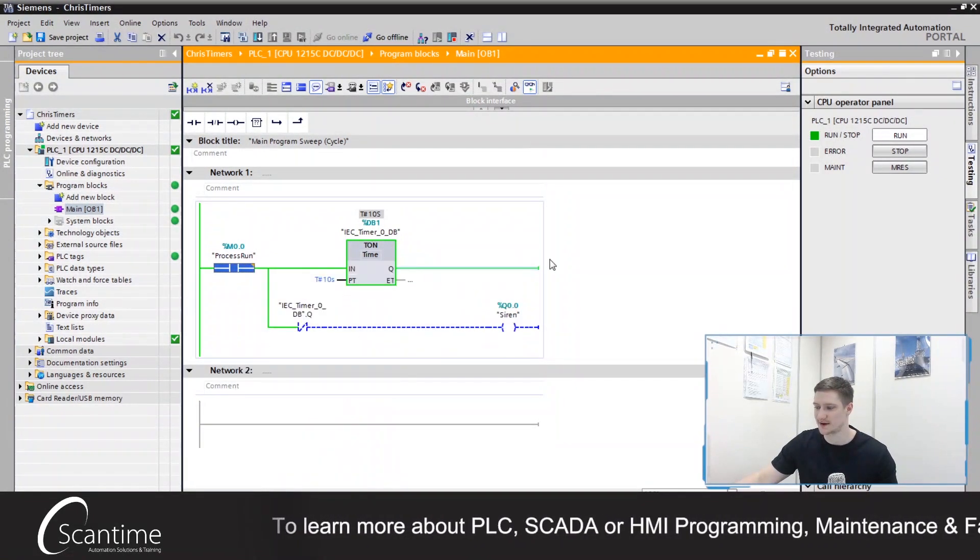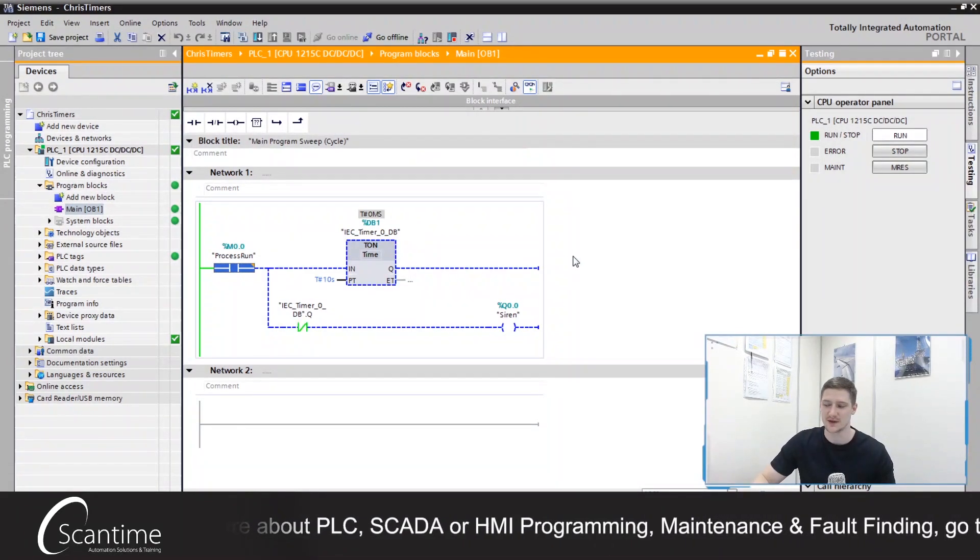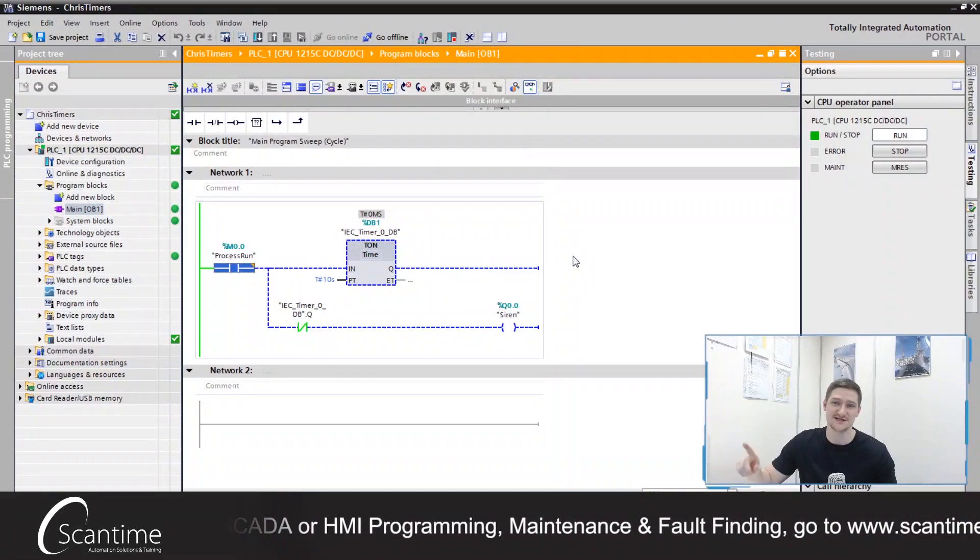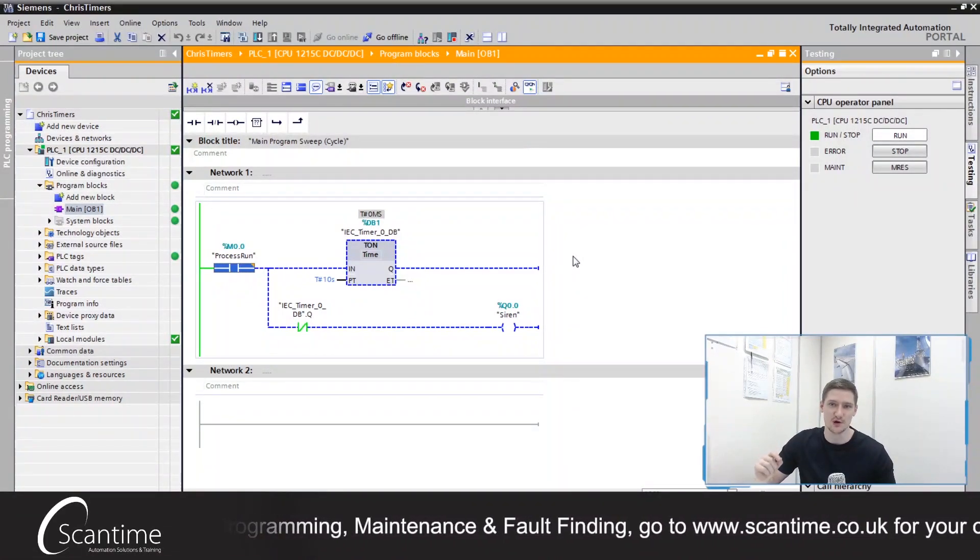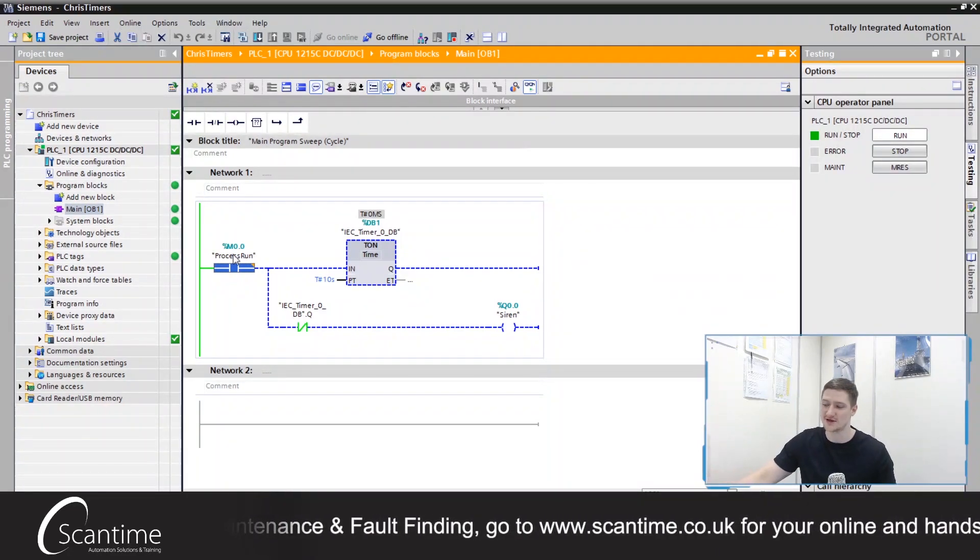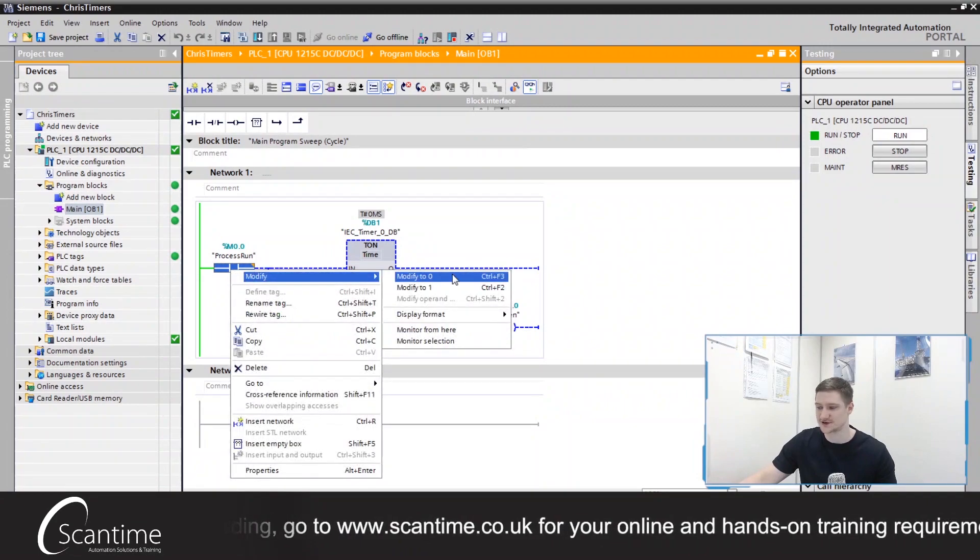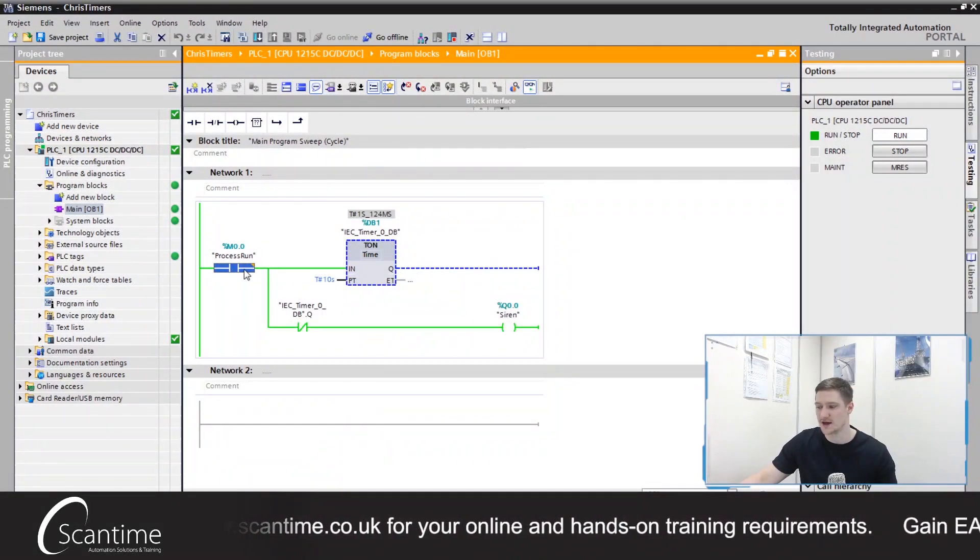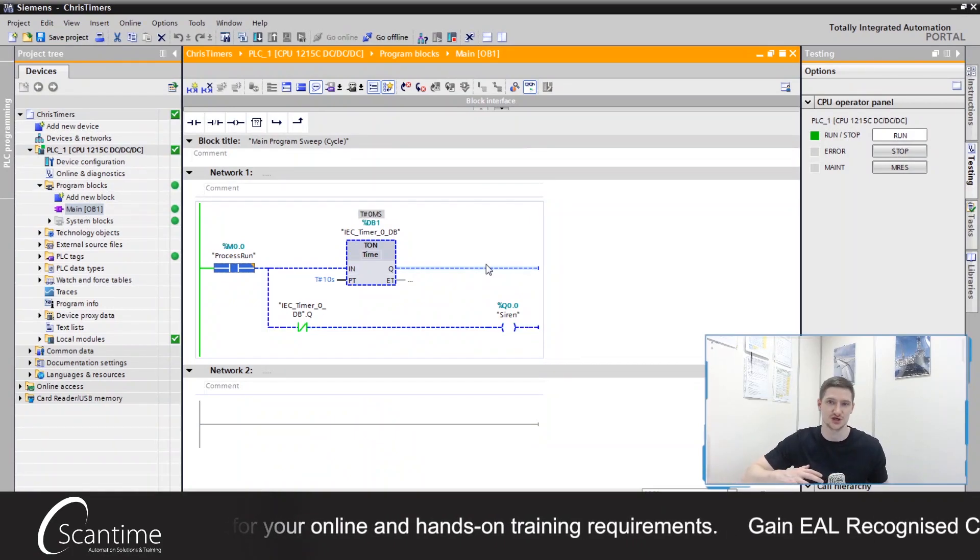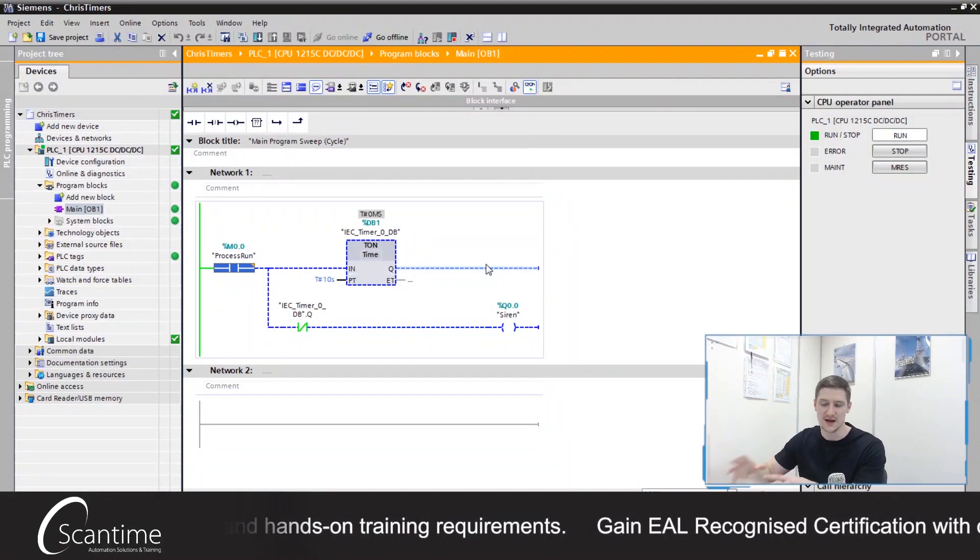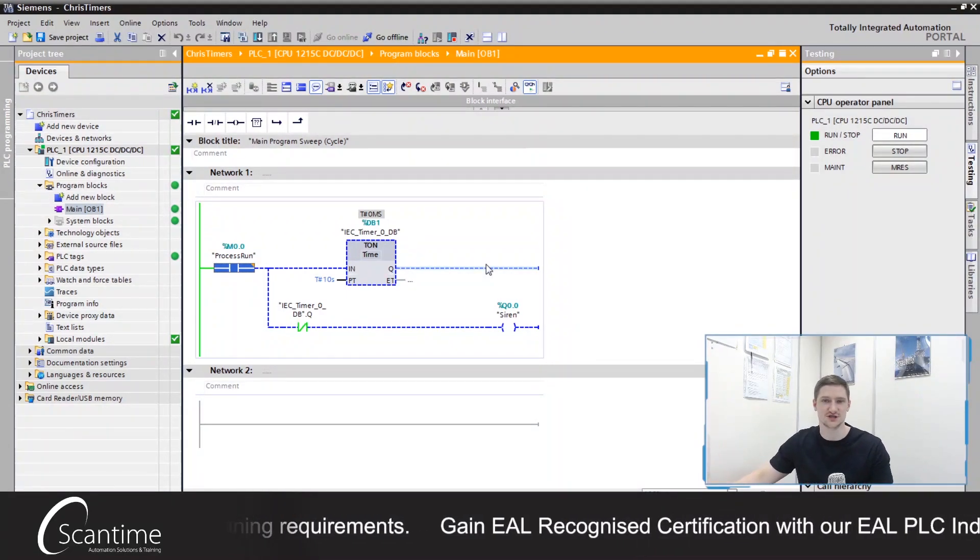So if we turn that back off again, it turns back off. Now if you actually think about the timer pulse in TIA, it only needed the signal to be on for one PLC scan. It didn't require this input signal to be on at all times. For example when I press this button here and turn it on, if I was to turn this off at any point, the whole thing just turns off. Whereas with the TP in TIA portal, it stays on until it's finished.